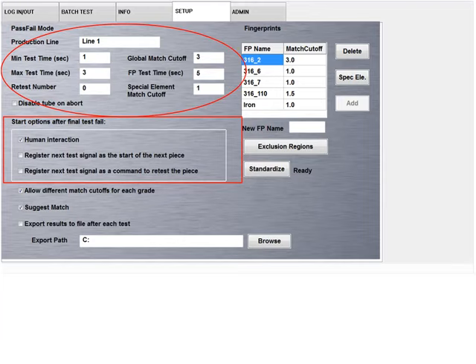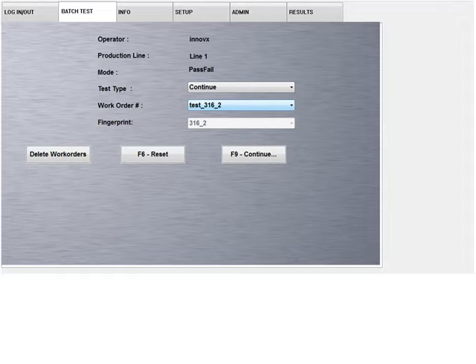Inside the rectangular region, we're looking at where selections are made about what to do if a sample fails. Some systems automatically move it into a reject bin. In some places a person has to come by to take it away. There's also the ability to set up a set number of retests before you fail a system. The batch test screen is where a production run is given a name and an alloy grade / fingerprint is selected from the alloy grade library to run the test. You can interrupt the test if you have to stop for some reason and then continue it.